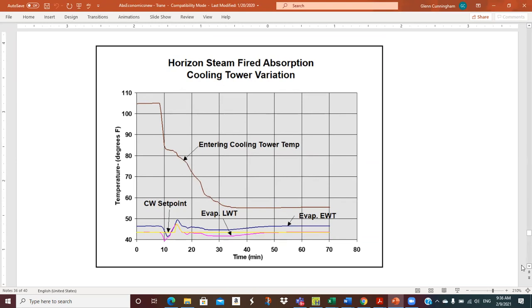So what they're doing now is they're going to monkey with the cooling tower, the temperature of the water leaving the cooling tower that's coming into the chiller. And they're going to start over here, oh my goodness, at 105 degrees. Well, you know, we usually expect to see 85. And so 105 is pretty darn aggressive. And then over, I think it's a 20-minute period or something, it looks like about 25 minutes, they're going to drop it to 55 degrees, which is a 50-degree drop. So let's see if we can screw up this chiller, you know, let's do our best.